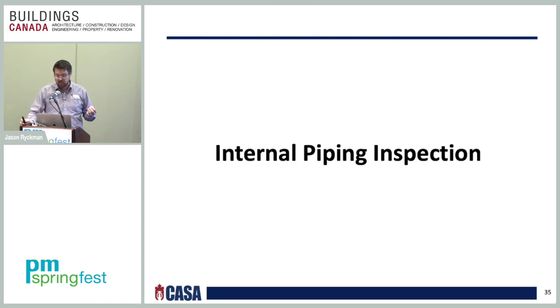Metal piping systems can lose structural integrity. Obviously, air and water don't mix very well, right? So ultimately, the corrosion can potentially become an obstruction due to corrosion byproducts, such as pipe scaling, we call it. The periodic internal inspections of pipe systems are intended to address this issue, okay? Piping obstructing material, sprinkler systems are no exception. Any maintenance program must include means for revealing potential obstructions and removing any obstructions that exist.